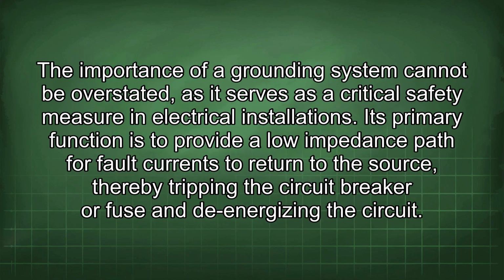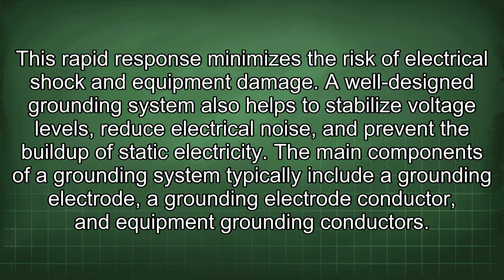The importance of a grounding system cannot be overstated, as it serves as a critical safety measure in electrical installations. Its primary function is to provide a low impedance path for fault currents to return to the source, thereby tripping the circuit breaker or fuse and de-energizing the circuit. This rapid response minimizes the risk of electrical shock and equipment damage.